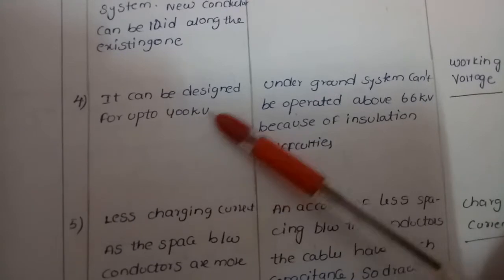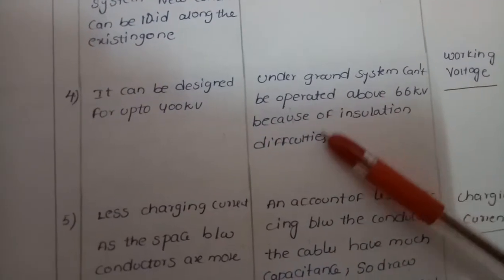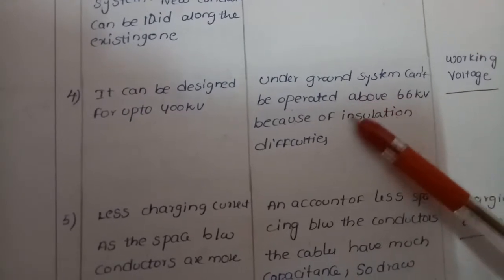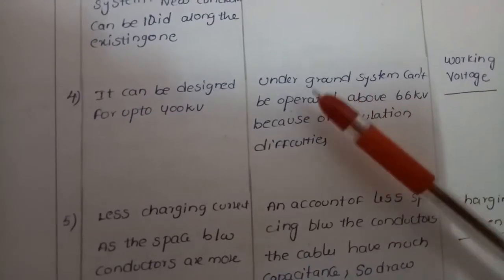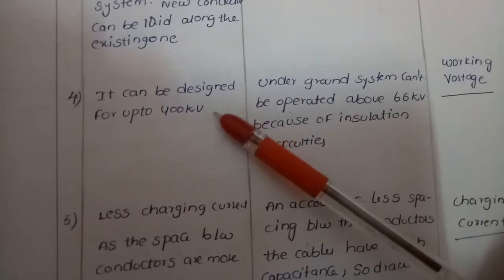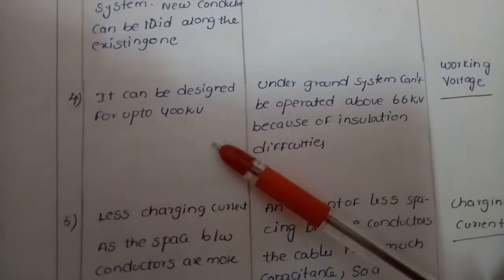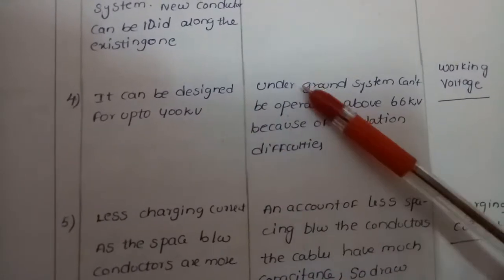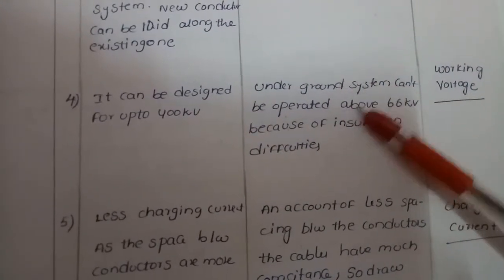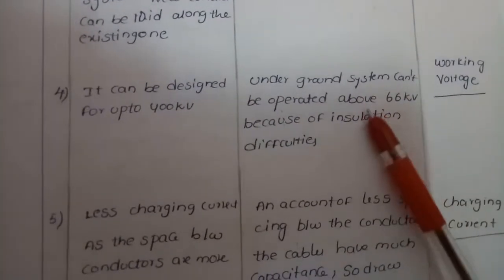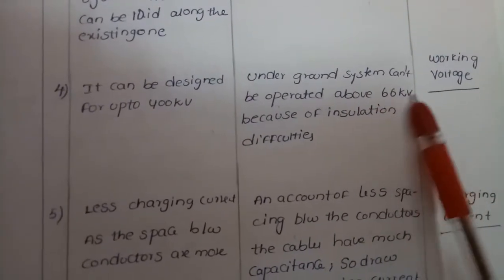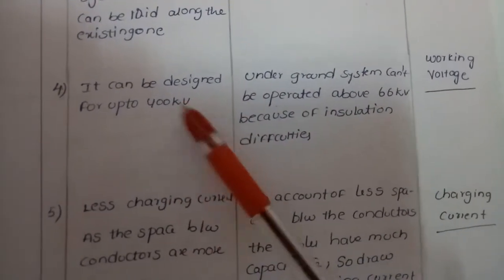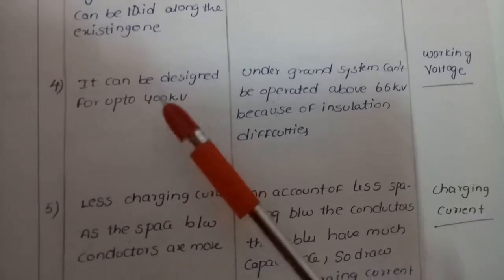Regarding working voltage, overhead systems can be operated up to 400 kilovolts, while underground systems cannot be operated above 66 kilovolts because of insulation difficulties. In overhead systems, more gap can be provided between lines to increase insulation, but in underground systems it is very difficult to provide insulation beyond 66 kV.